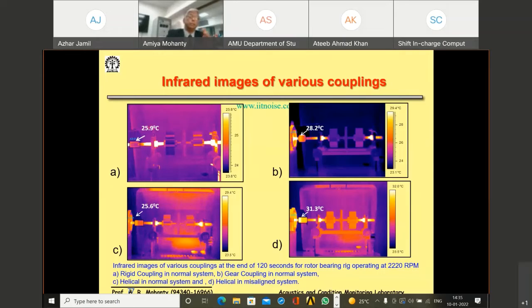And this can very easily be captured by a thermal imaging camera, where we are collecting data, maybe 30 frames per second or even 60 frames per second. These videos were being collected, and then we plotted the temperature curve. So what I mean to say is, permanently we can embed certain temperature sensors, sample them at 30 or 60 frames per second, and monitor the temperature.